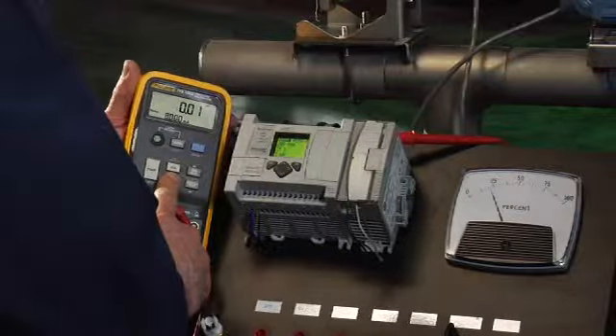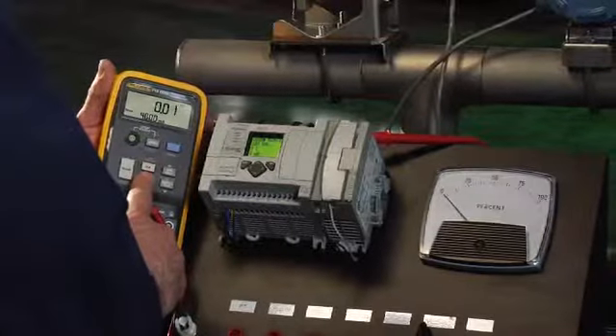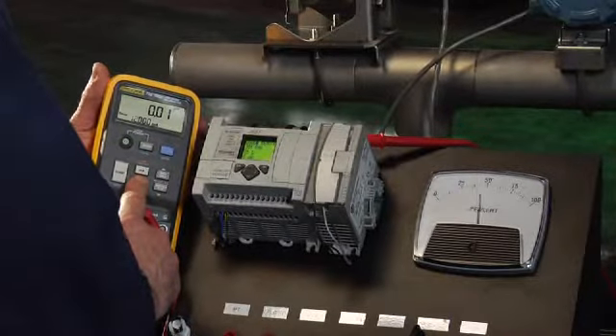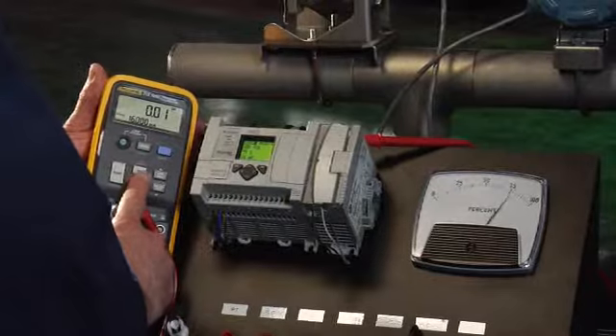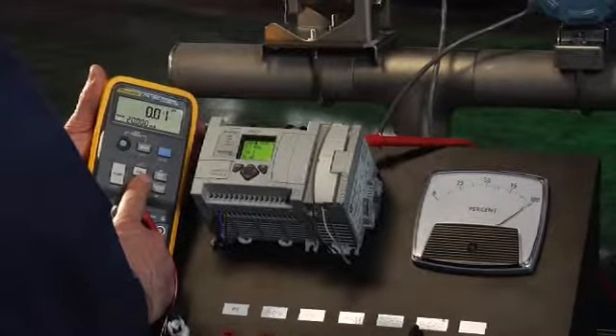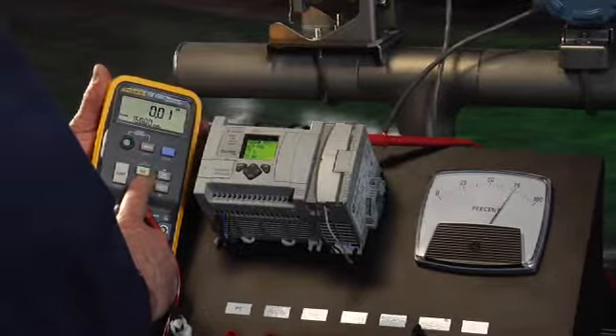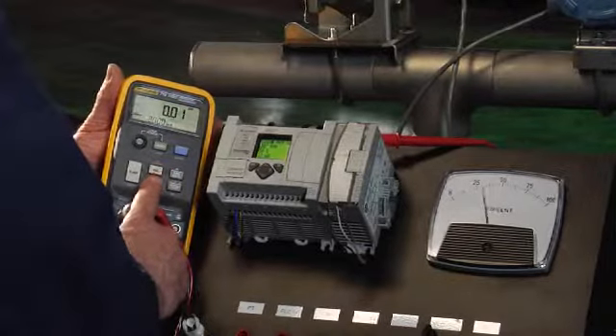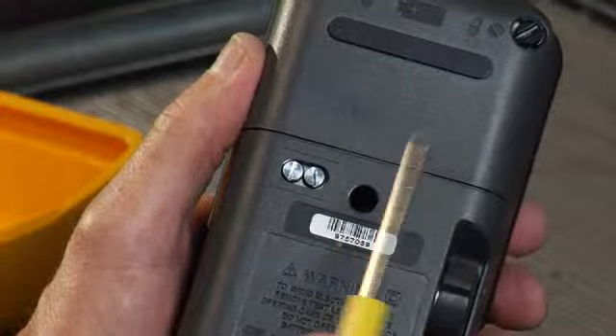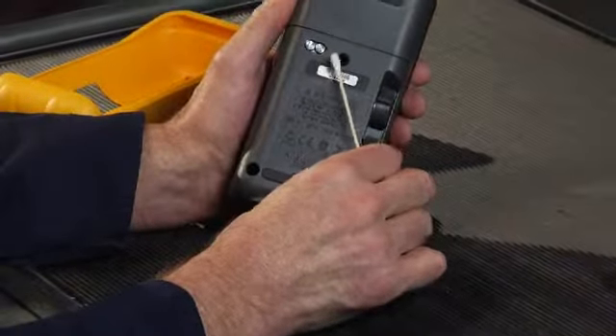One key feature of the 719 pressure calibrator and our 718 pressure calibrators is the cleanable pump. In the event that you catch fluid inside the unit, you can open up the cleanout valves in the bottom of the 719 and remove the fluids. You'll need a slotted screwdriver to access the cleanouts and a cotton swab to clean out the chambers.